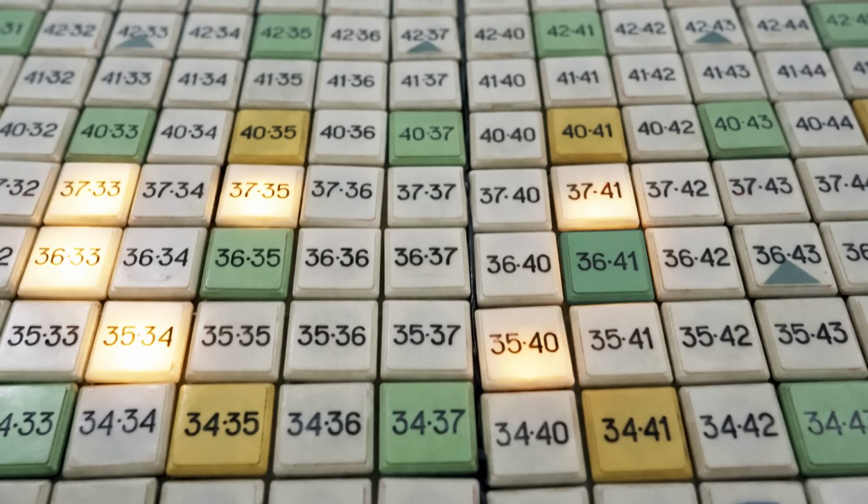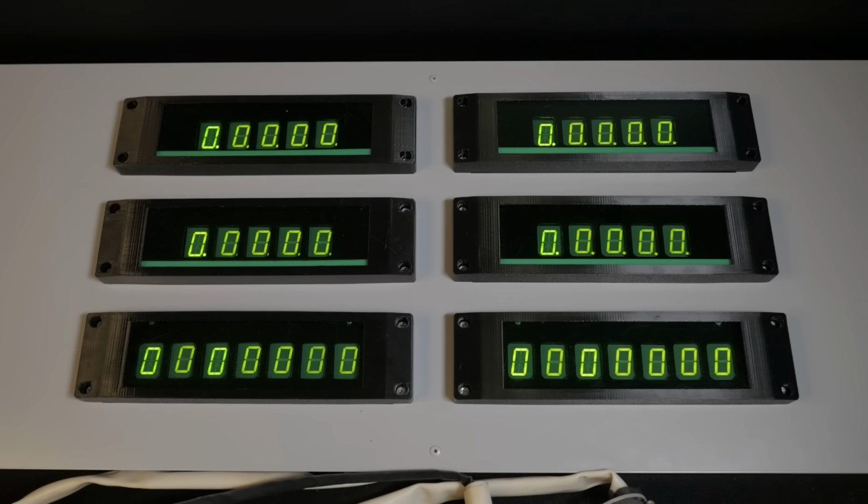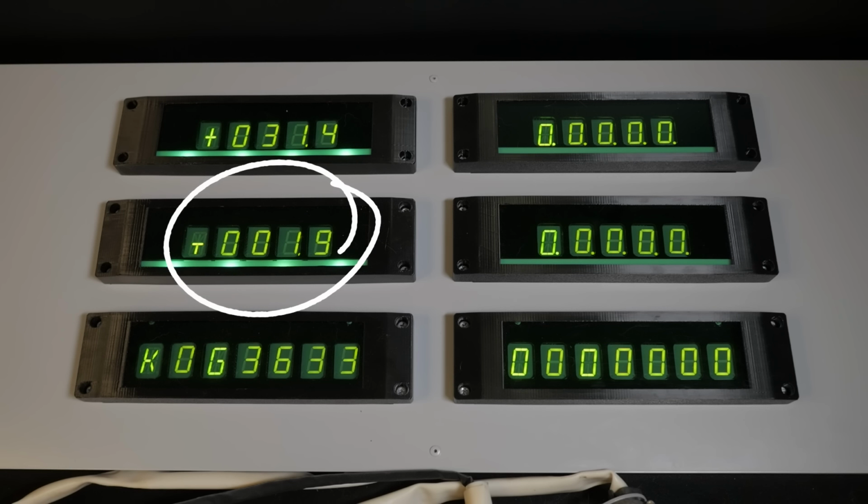The illuminated squares indicate channels where coolant flow is too low. Using coordinates we now can select one of the highlighted channels and investigate it. This is a very real-life situation, so first I request its coolant flow. The result is lower than normal, but this reduced flow alone doesn't tell us how dangerous the situation is.